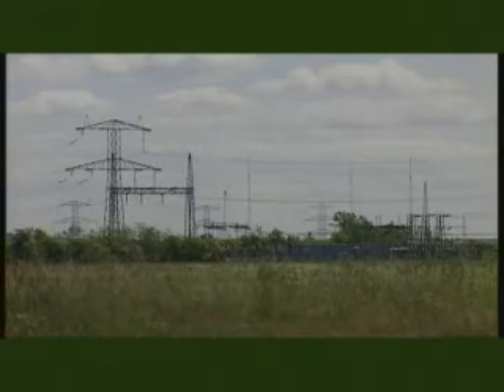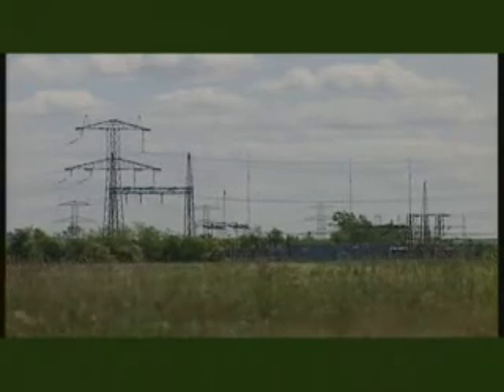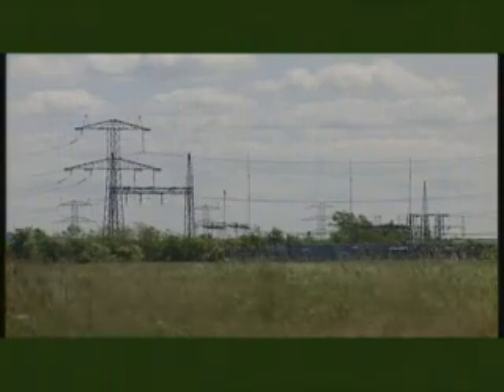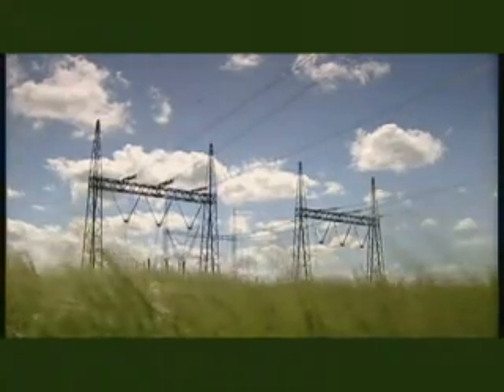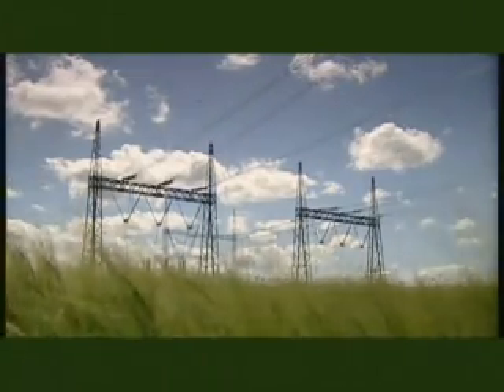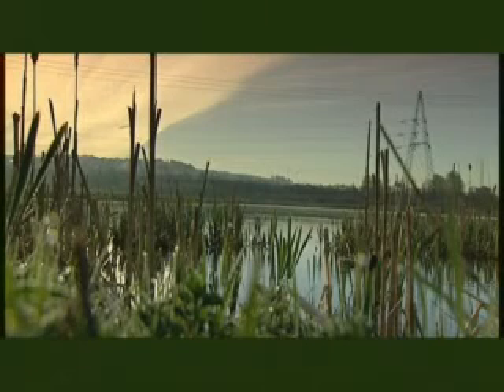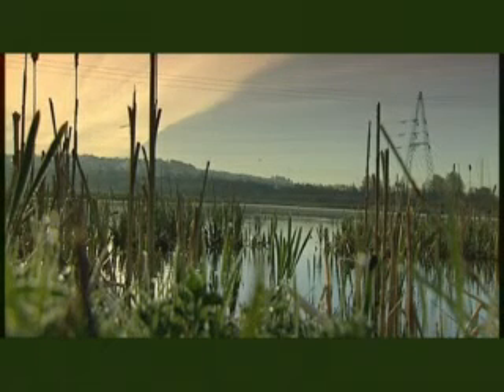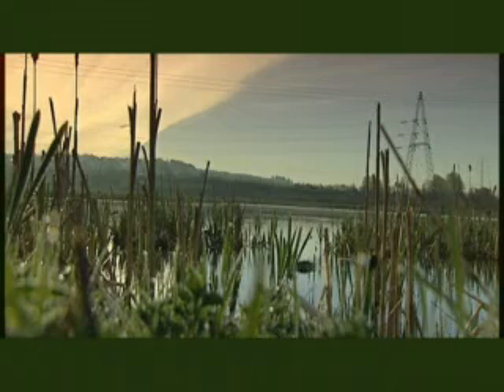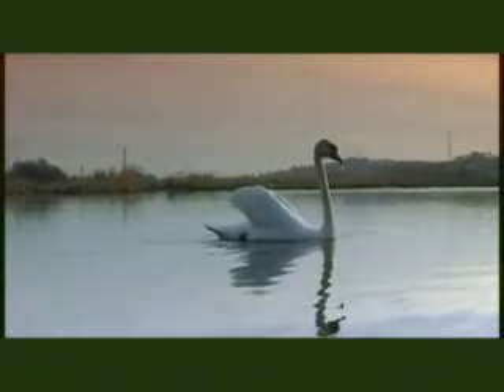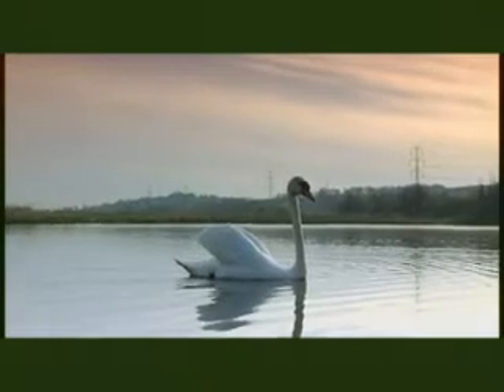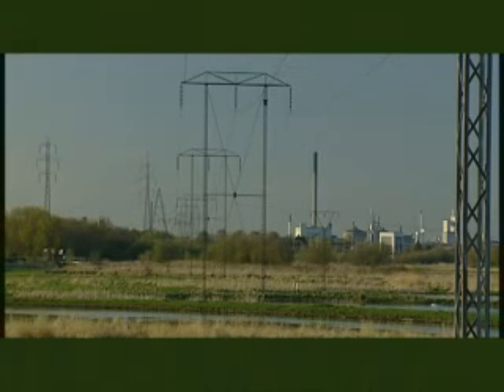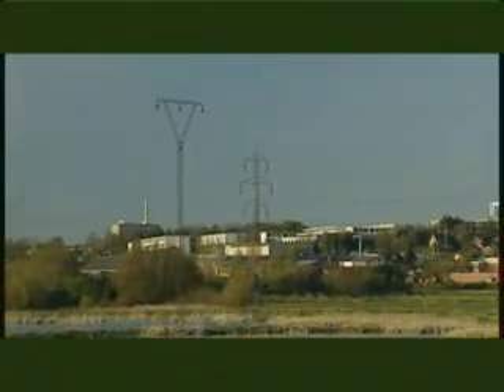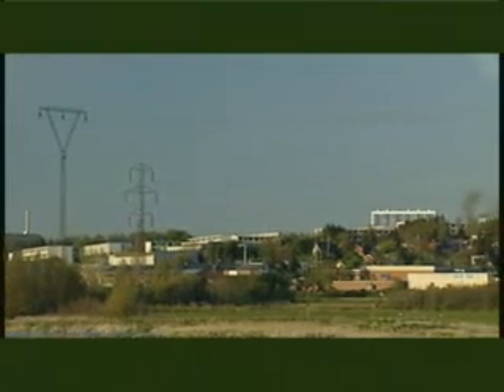The section from Skudshale to Gistrup runs through a water catchment area and through a plantation where growing conditions are relatively poor because of a chalk layer just beneath the surface of the soil. This part of the cable route is quite unlike the low and very damp area through Inkilderdalen, which makes up the longest cable section, 7.5 kilometres in all. Drainage pipes were laid before cable trenches were dug in the wet areas. Drains have also been laid on top of the cables to prevent the soil from becoming soft in the years immediately following the cable laying.